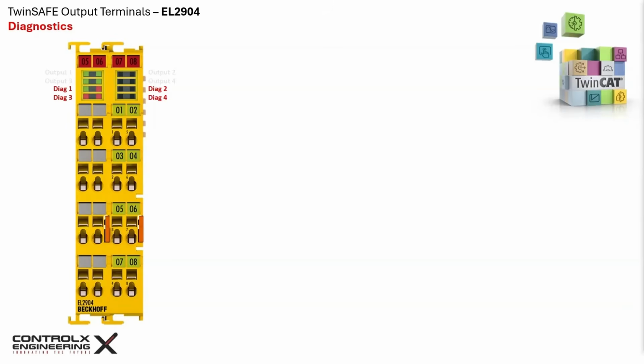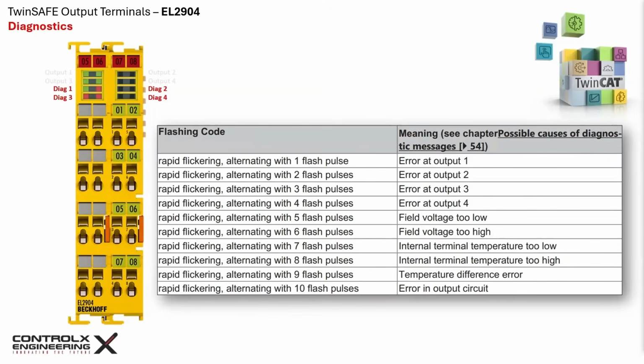Diagnostic 1 green LED indicates the state of the TwinSAFE interface. Diagnostic 2 red LED indicates the fault state of the digital outputs. The number of flashes indicates if there is an error at one of the output channels, if the voltage is too high or too low, as well as faults regarding internal temperatures.